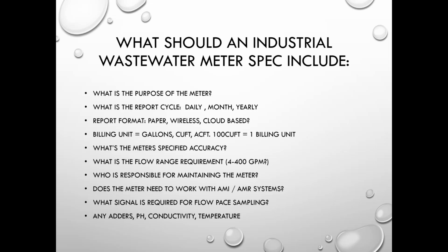What's the meter's specified accuracy? That's a big question, and believe it or not, many industrial clients don't really ask it. It's just, I need a meter and I'm not 100% certain what the accuracy is, just give me the most accurate meter. And then the big question is, what is the requirement for your flow range? In other words, do you know what your facility puts out in minimum and maximum flows? Then we need to put in a meter that is going to operate in that range.